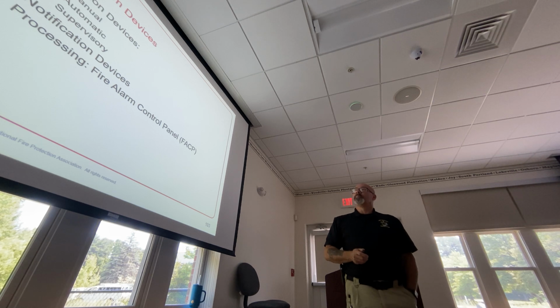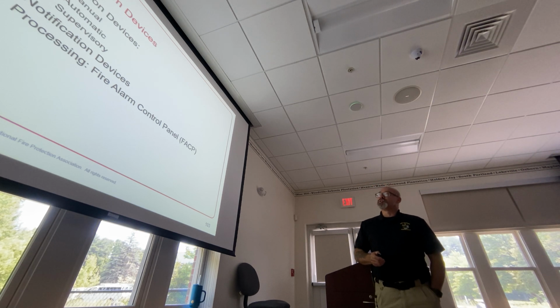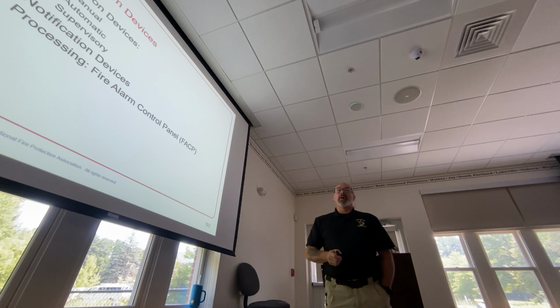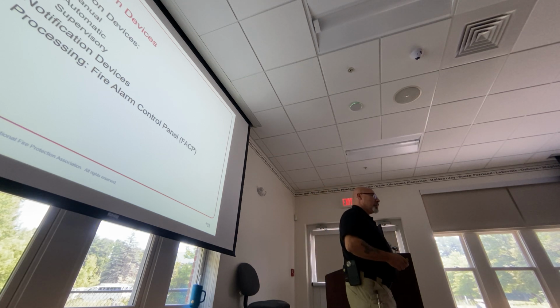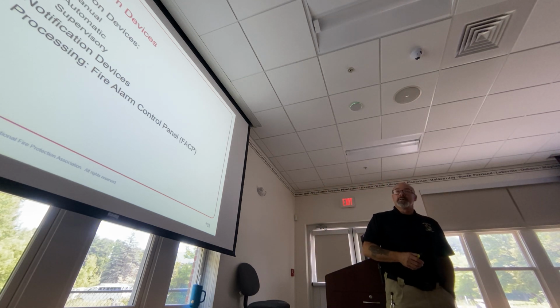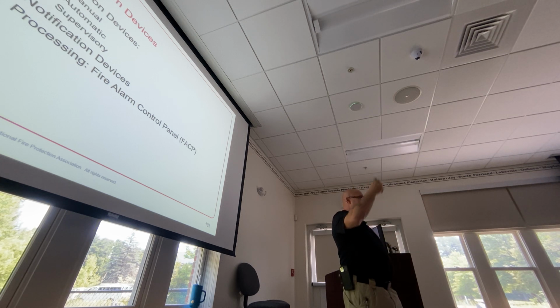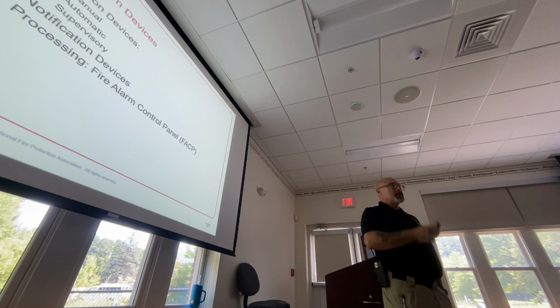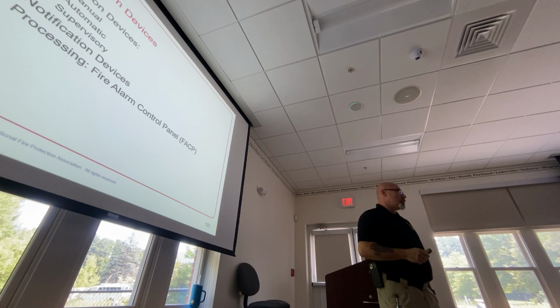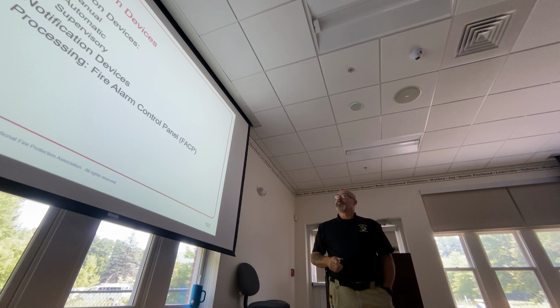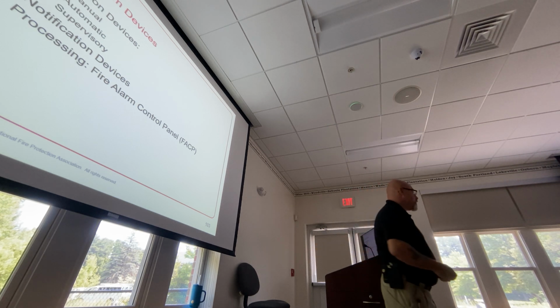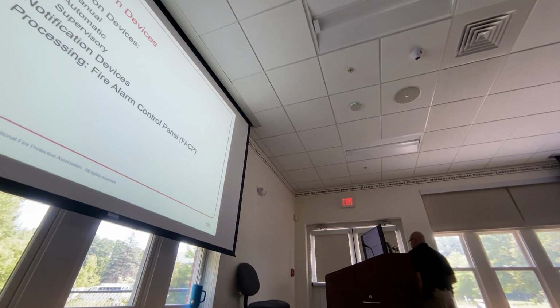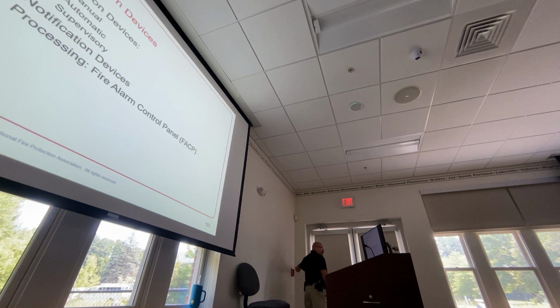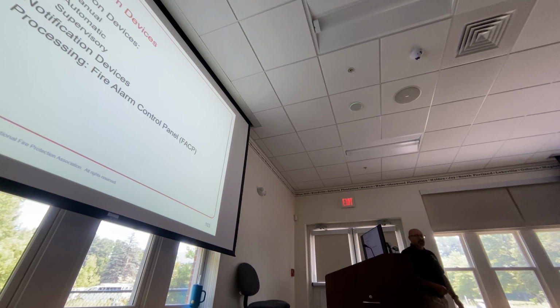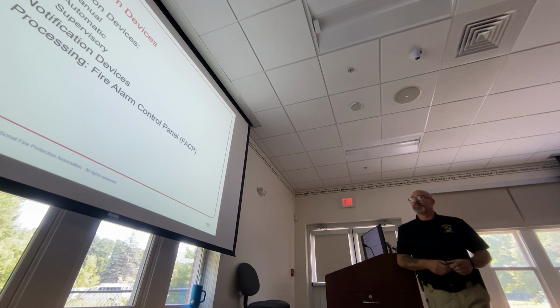So, super basic on the components. Initiating devices can be automatic. Automatic initiating devices are something like a detector. It detects that there's flames or smoke and sends a signal back to the system. It could be manual. This is a manual pull station, for those of you who can see it at the doors. That is a manual initiating device.